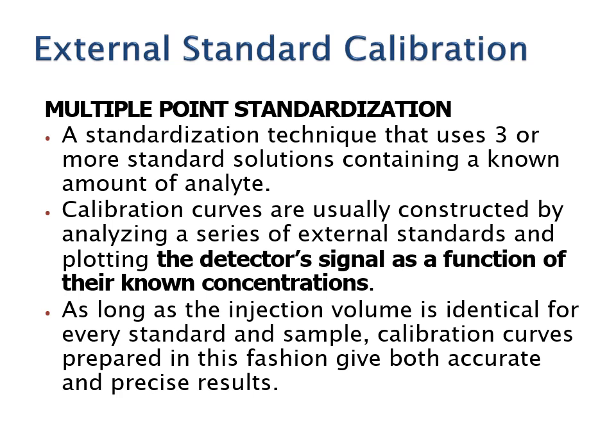Next, we have multiple point standardization, a standardization technique that uses 3 or more standard solutions containing a known amount of analyte. Calibration curves are usually constructed by analyzing a series of external standards and plotting the detector signal as a function of their known concentrations.